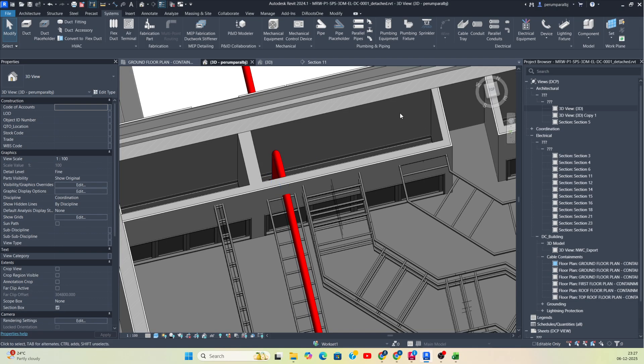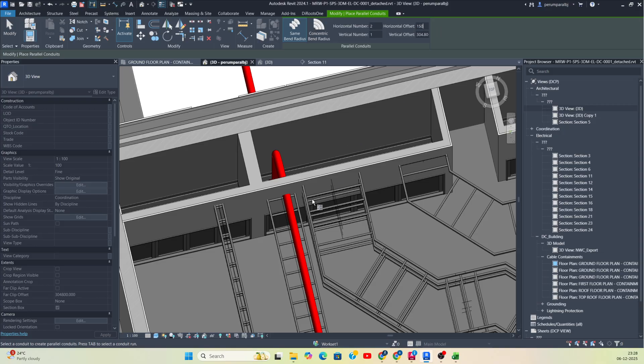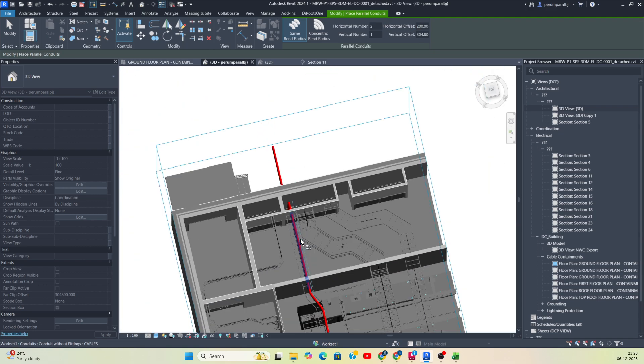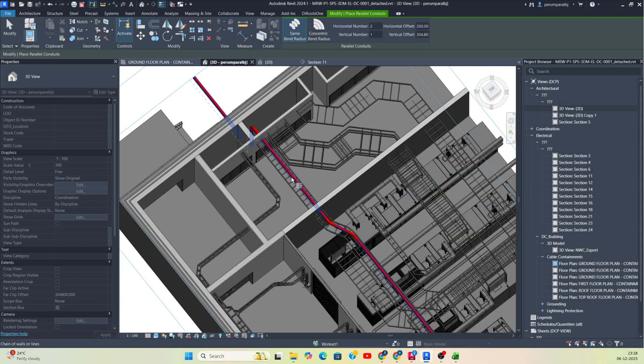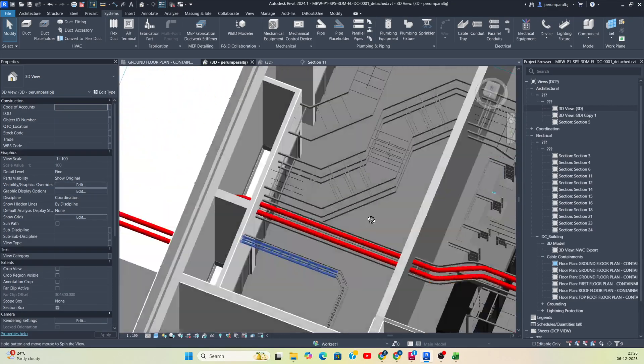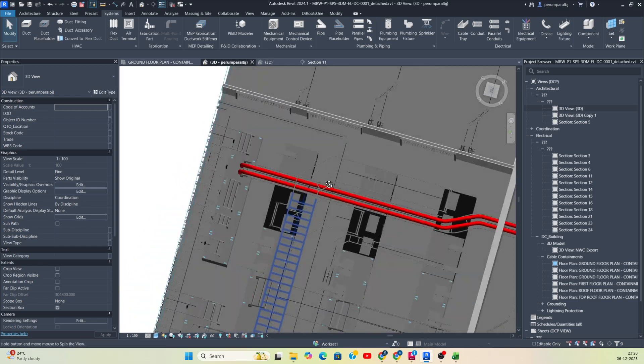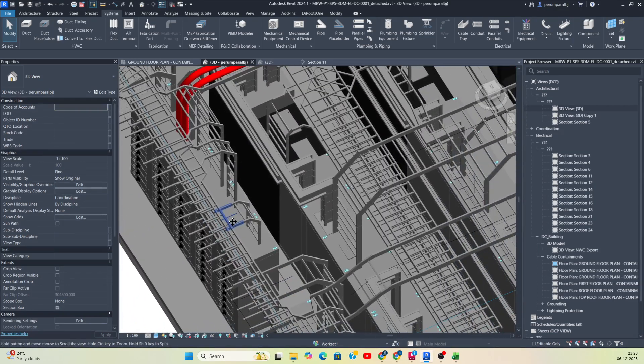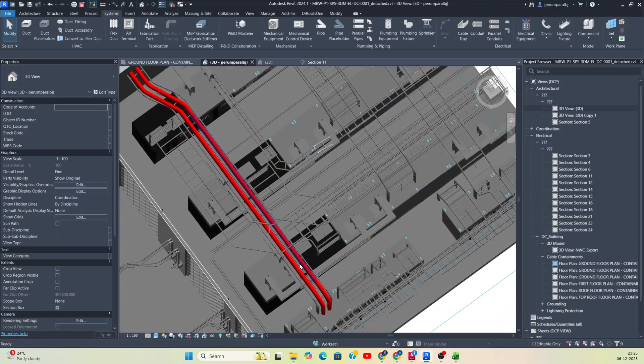If you need to run one more conduit, go to Parallel Conduit. I want only two, and for the spacing I can give 150 or 200 — let's give 200. You can see it's selecting. Just hover above the conduit and tab it — automatically it will generate one more conduit. That is the use of the parallel conduit. You can run conduits to the panel like this.